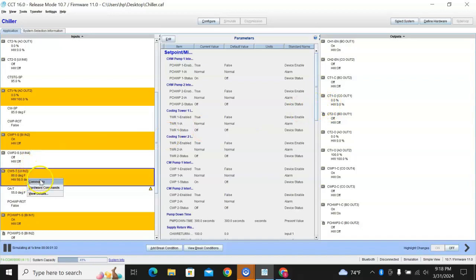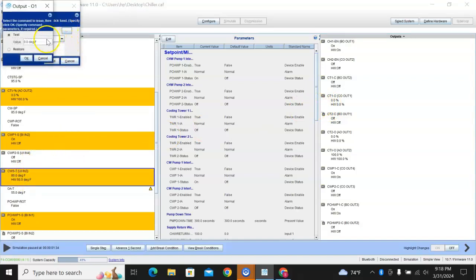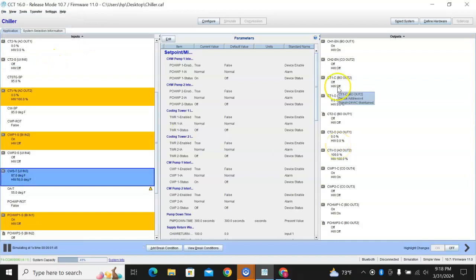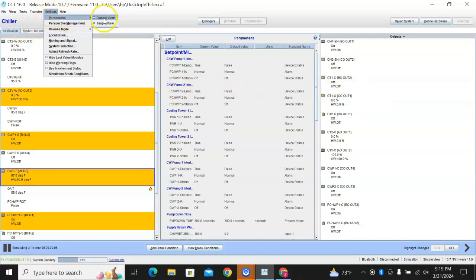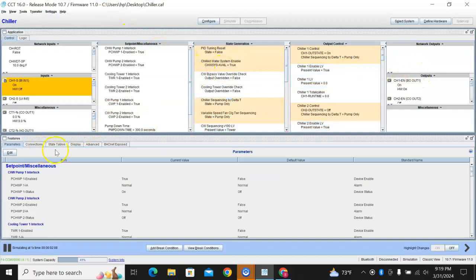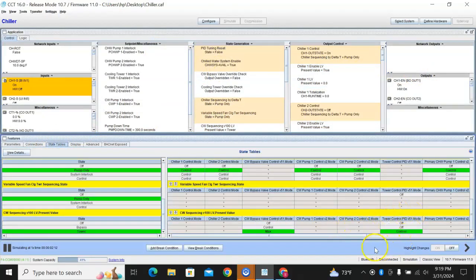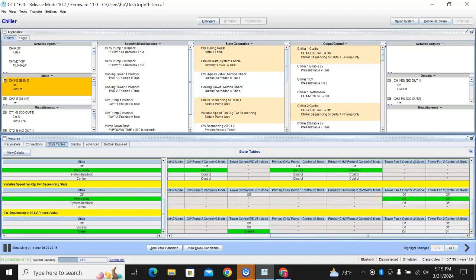So I'm going to go ahead and give it another one here. 87. Show you what's going on if you want to see. It's really not the cooling tower's fault. It's not the PID's fault right now. It's because we just started this. We go to the states tables to see this. If I go all the way down here to the bottom, I can see that right here, this variable speed cooling tower is in pump only. So it's really just the startup value of this. But as soon as this goes down to control, it's going to hit. Put this back into simple view.